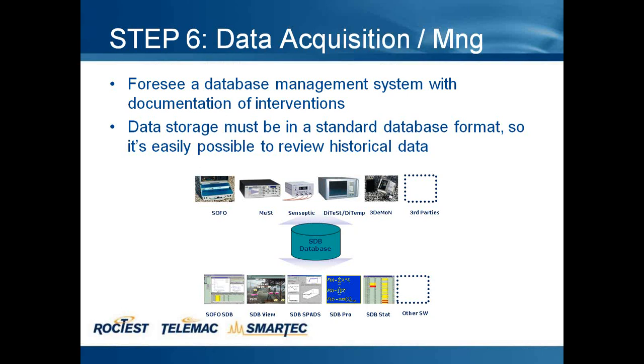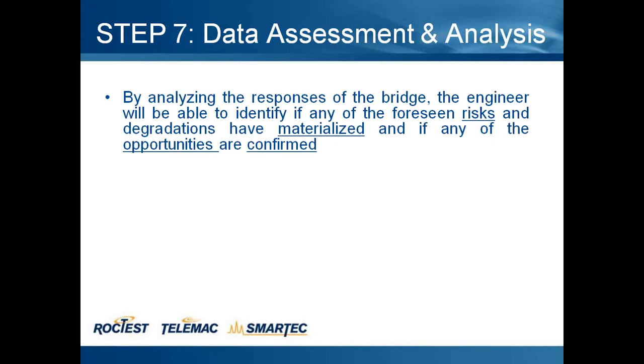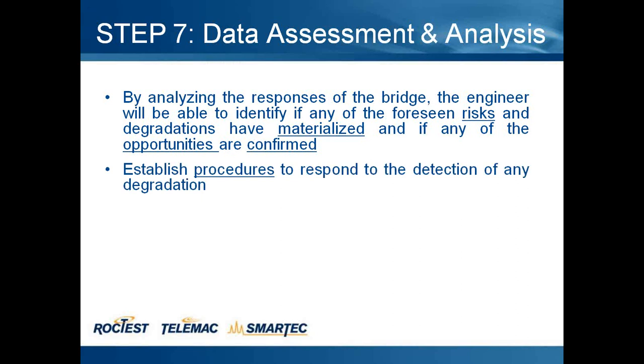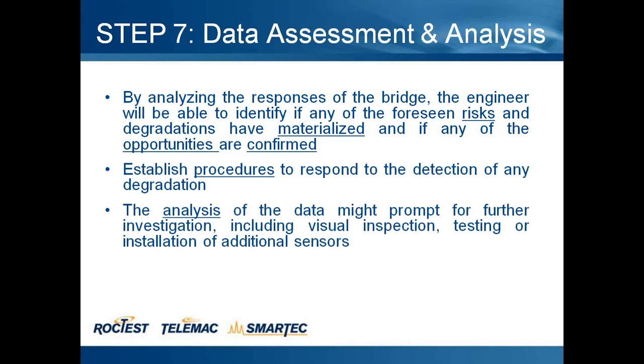The last step is data assessment and analysis. By analyzing the responses of the bridge, the engineer will be able to identify if any of the foreseen risks and degradation have materialized and if any of the opportunities are confirmed. It also consists of established procedures to respond to detection of any degradation, and the analysis of the data might prompt further investigation including visual inspection, testing, or installation of additional sensors. It's also possible to set alerts, warnings, and periodic reports.